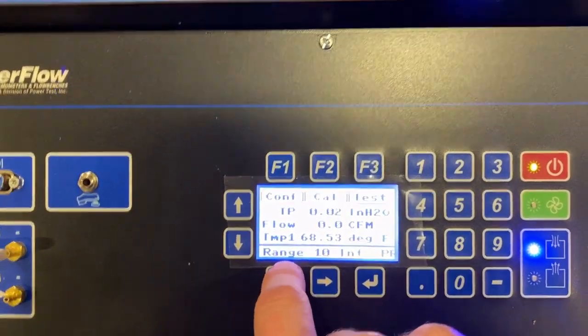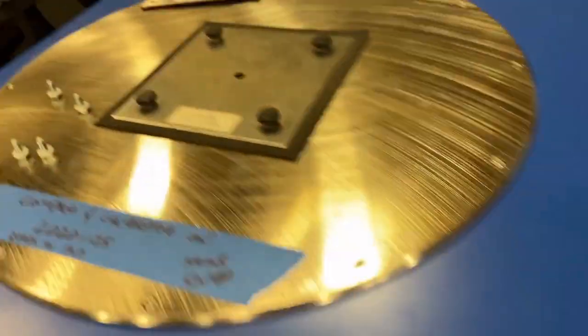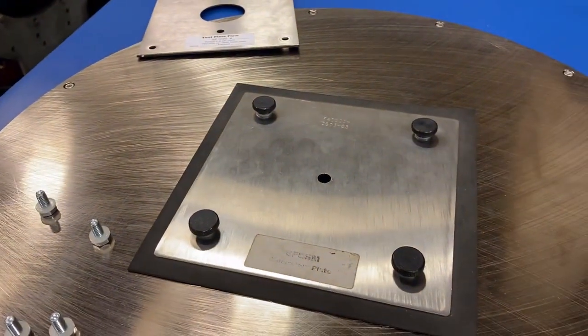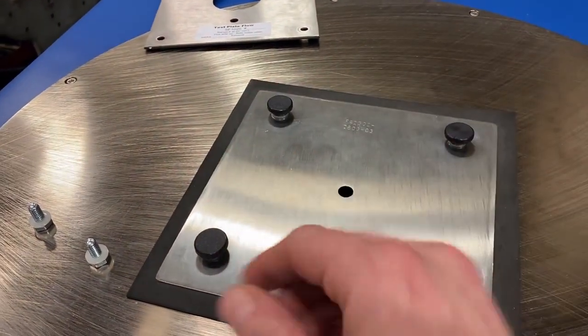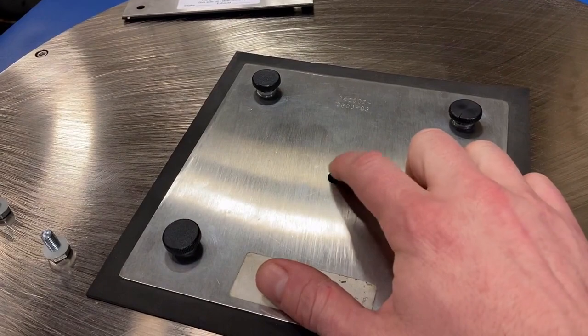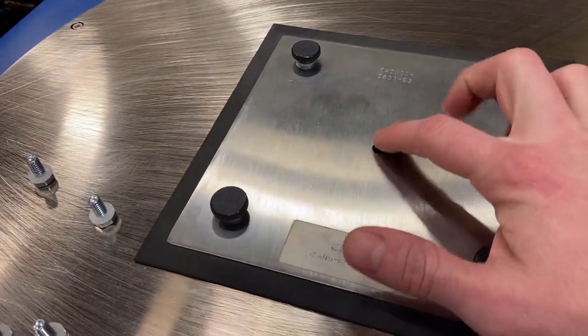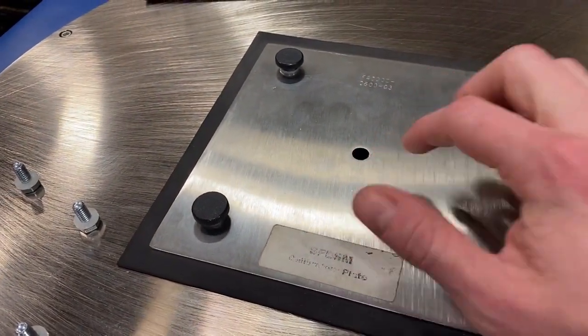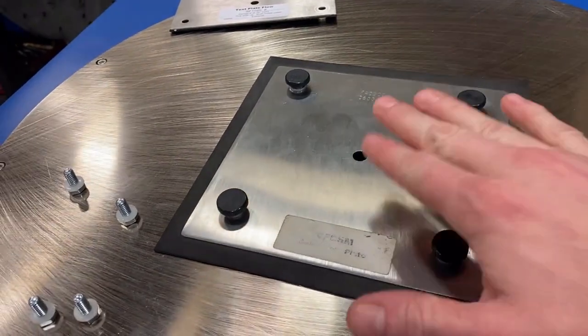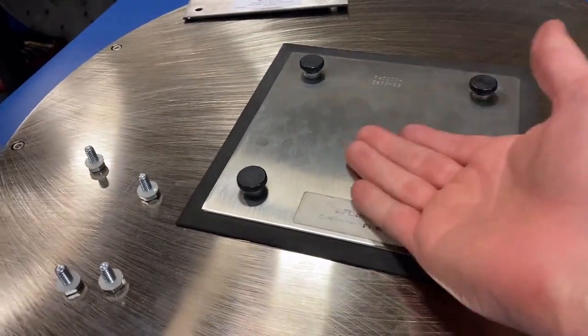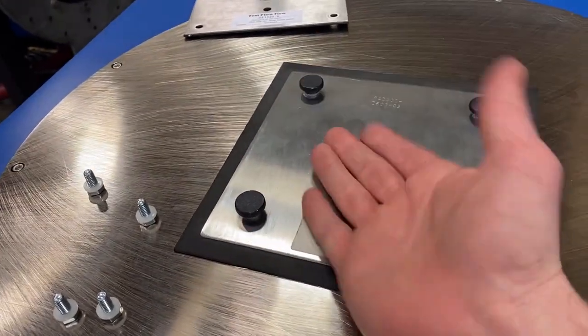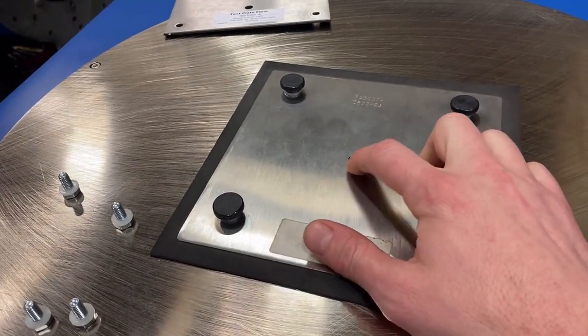We would do the same thing for exhaust, except in the exhaust setting, we would actually flip the plate over, because the edge here is a machined edge specifically for intake. And so obviously if we have the exhaust setting where we're going to be blowing air out, we want to have the plate flipped over so that this edge faces the airstream.